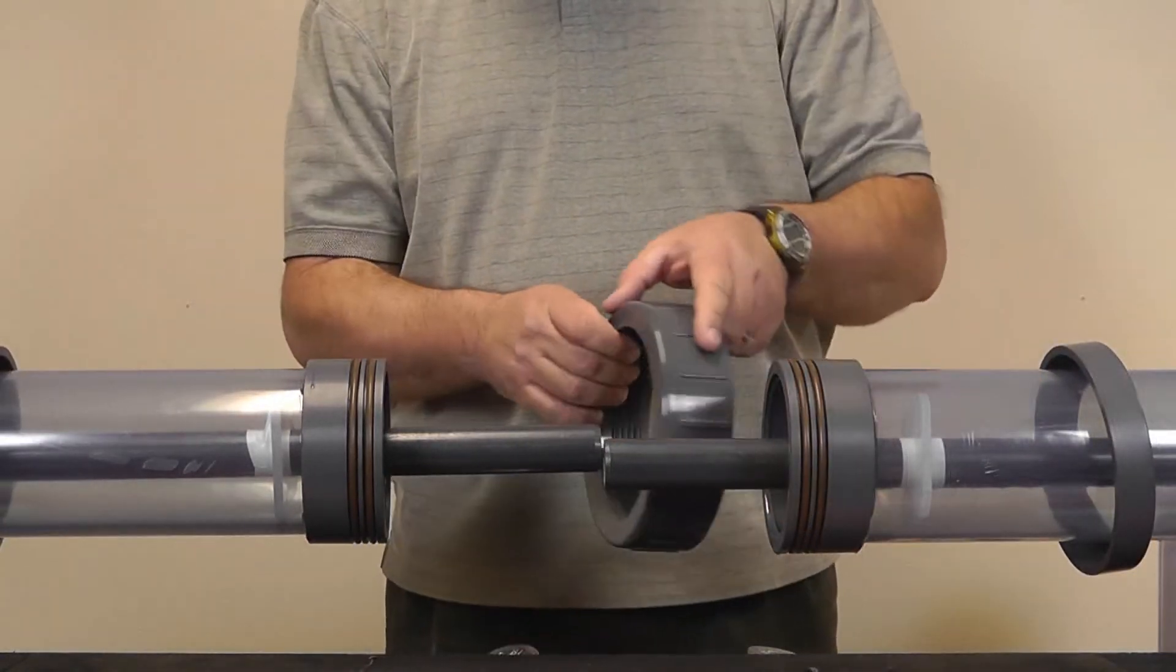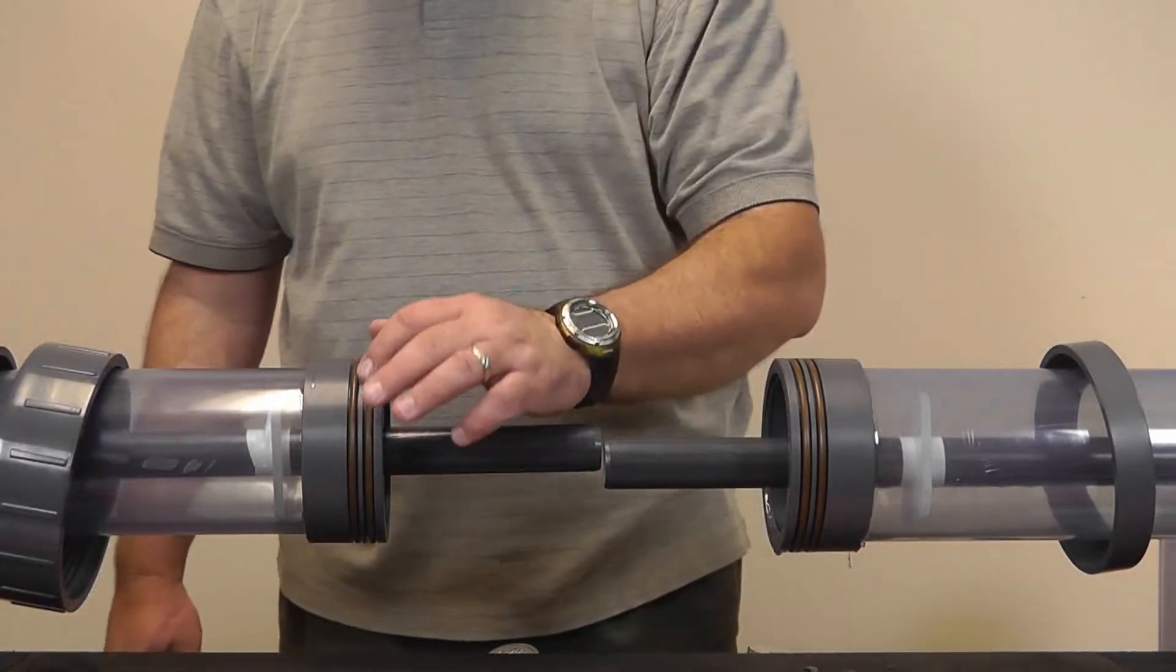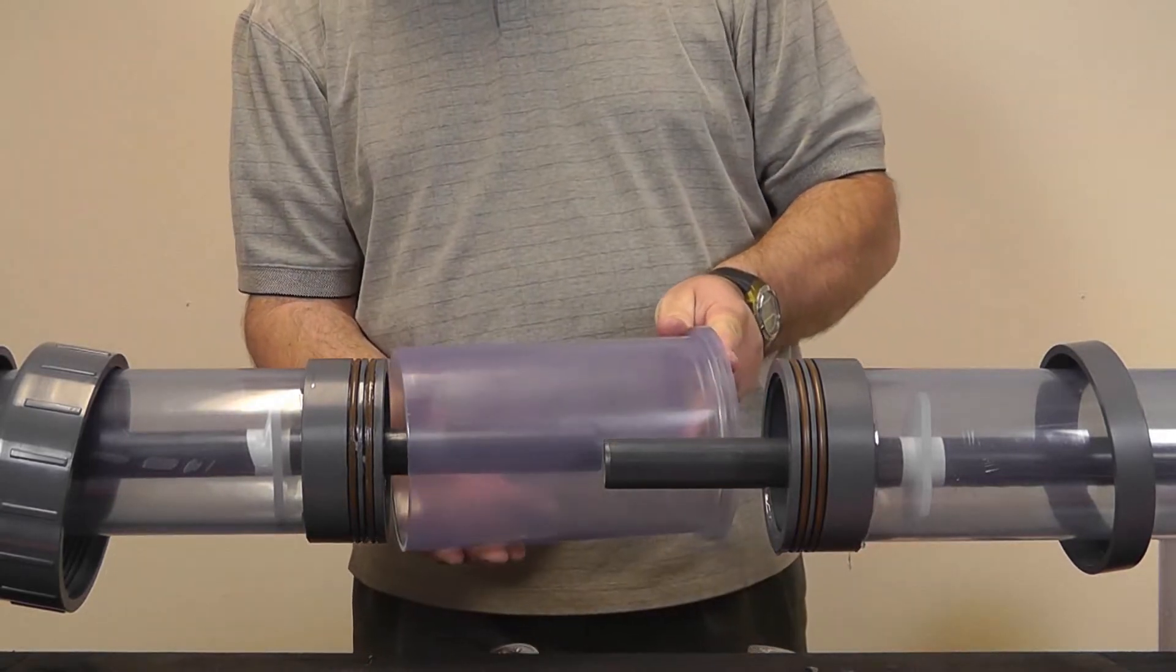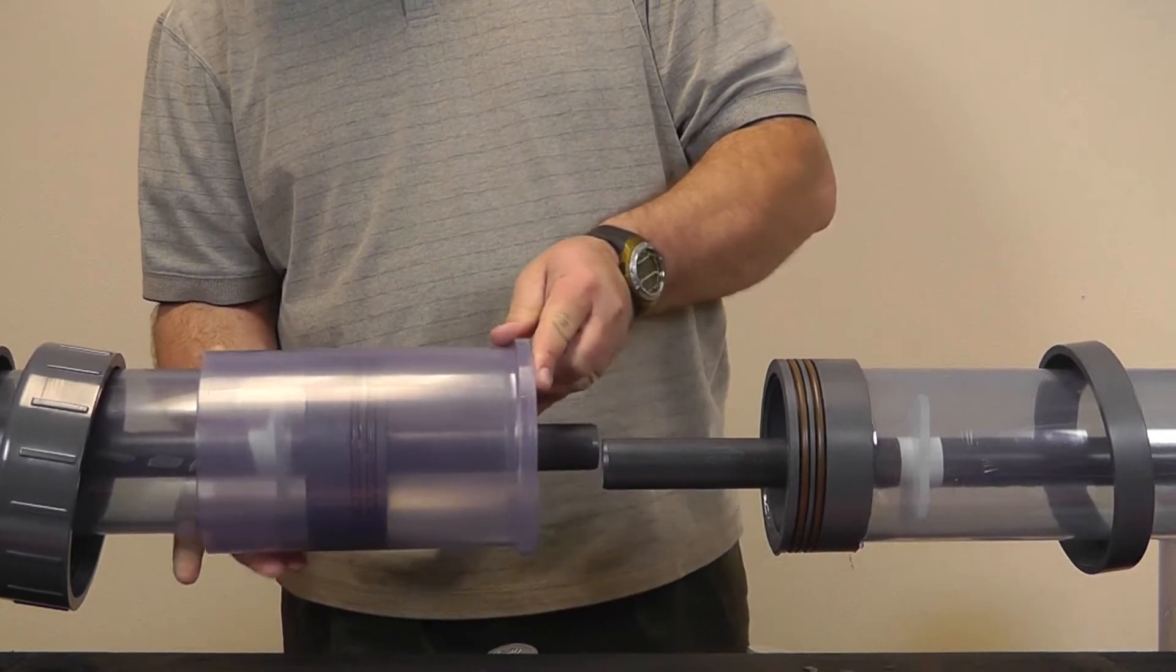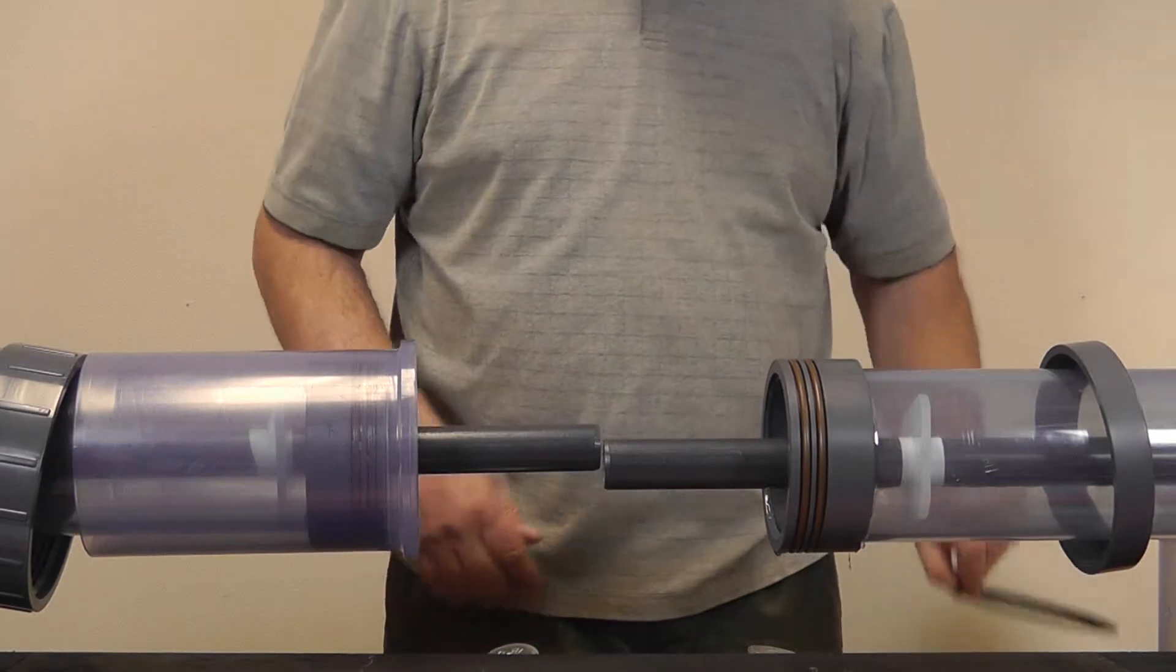Now install the union nut, then using the supplied silicone, apply silicone to the O-rings on the seal carriers, making sure that you don't get any silicone on any of the PVC that needs to be solvent cemented. Then install the two body halves and install the union O-ring.